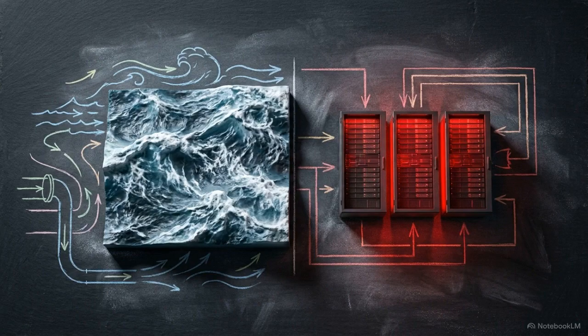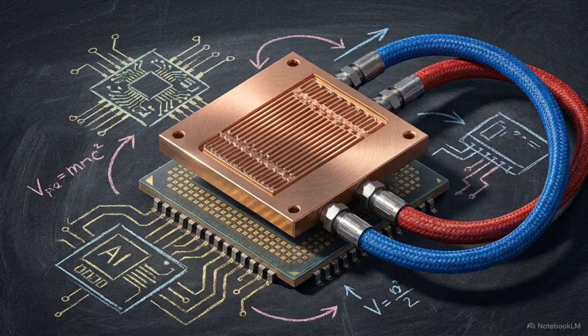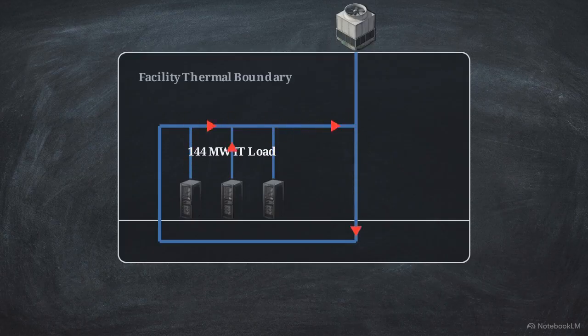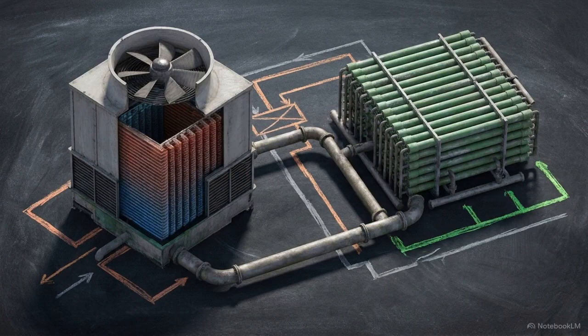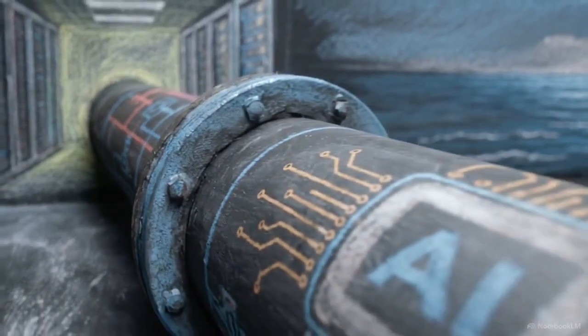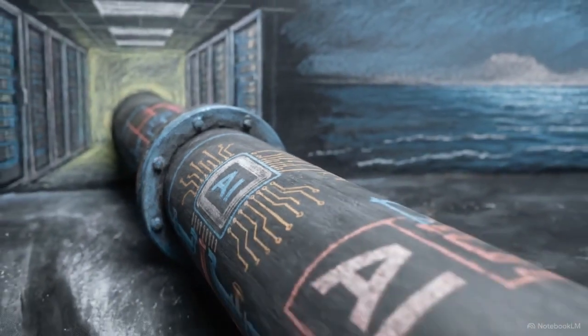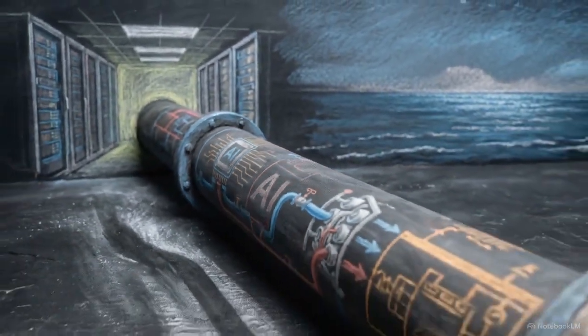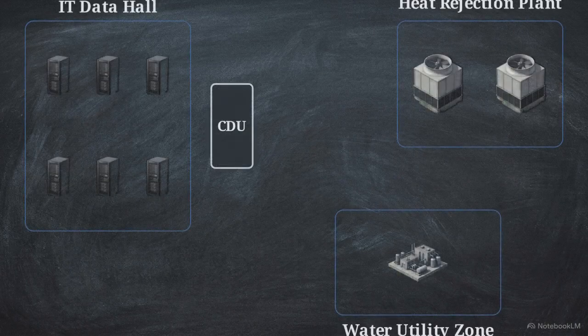Integrating desalination into the thermal path requires adhering to a fixed thermodynamic reality. Direct-to-chip liquid cooling does not eliminate heat, it concentrates thermal energy into a high-density liquid loop. Every megawatt generated by the servers remains trapped within the building's hydronic systems until it is physically rejected to the atmosphere. To maintain uptime, the facility's heat rejection and water supply cannot be managed as separate utilities. Instead, they must be engineered as a single continuous chain running from the processor silicon out to the sea. This system map details the requirements for moving that heat.